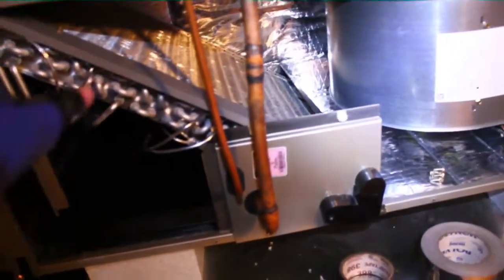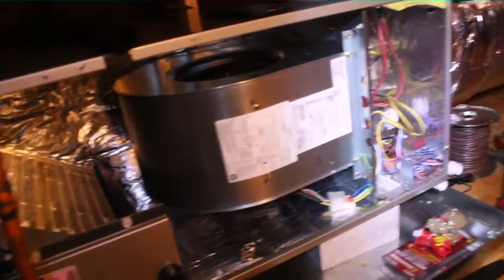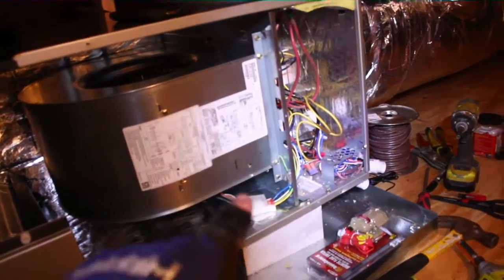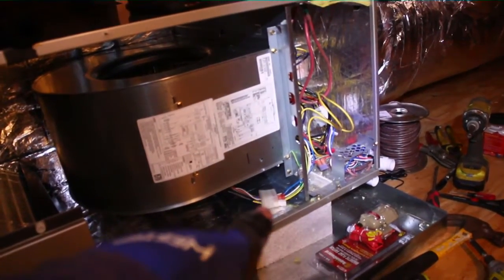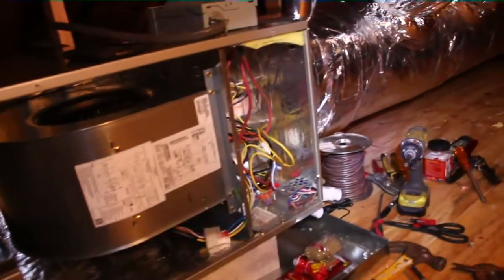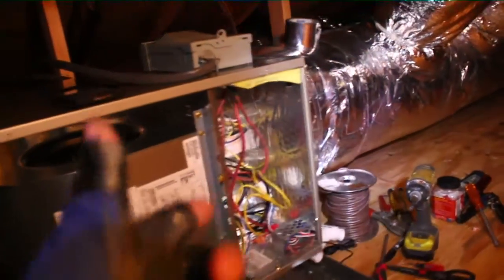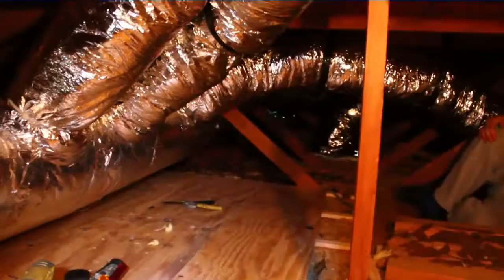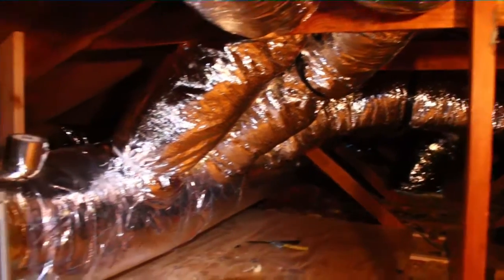We have a return behind us. There's our return box. It gives you plenty of room to mix the air. Aluminum slant coil. I think the last one was copper, but this one's aluminum this time, or tin coated copper. X13 motor. Actually set it up with the same blower taps I used on the previous job, since it's the exact same motor. 8 kW, and our ductwork is done. So we're going to move on to putting nitrogen on it for the night, and start it up in the morning.